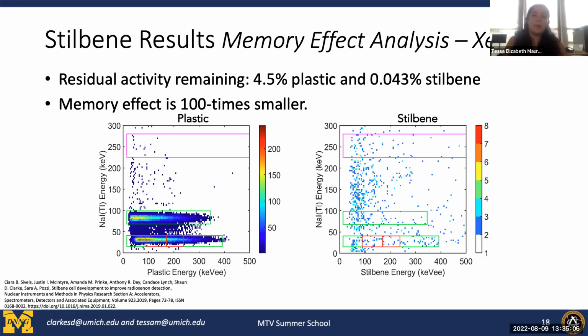And so these figures show exactly that, especially the one on the right. After some time has passed after evacuation, you can see the plastic scintillator still has radioxenon present in it. It's still popping up, showing that radioxenon is present, and specifically 4.5% of the sample was remaining in the plastic, which is pretty significant and will affect the minimal detectable concentration and could lead to things like false negatives and so forth.